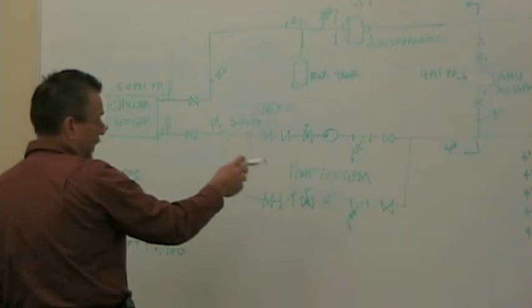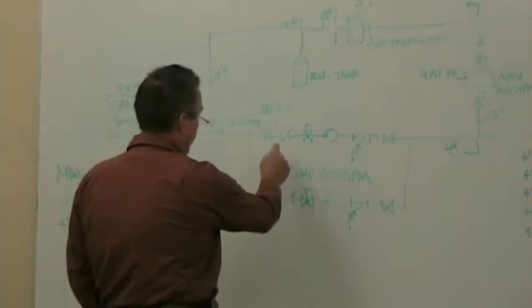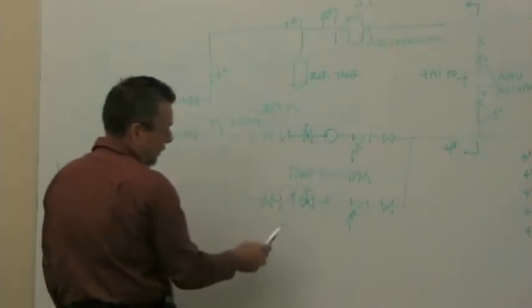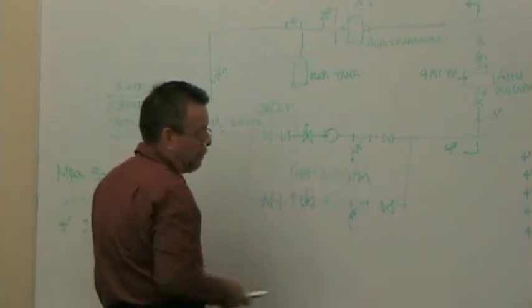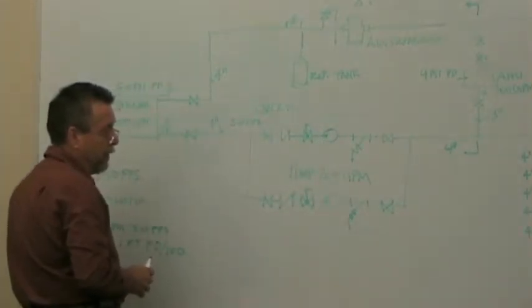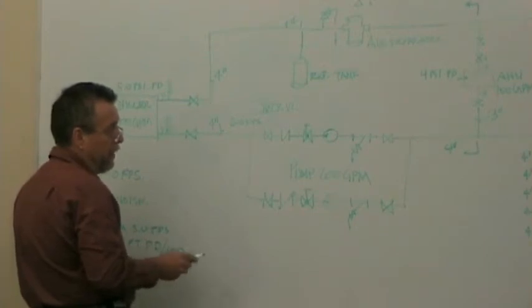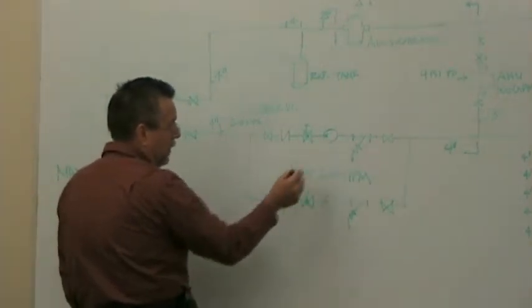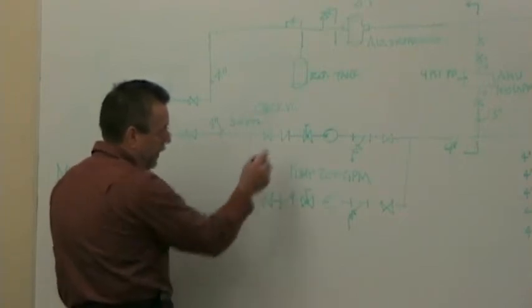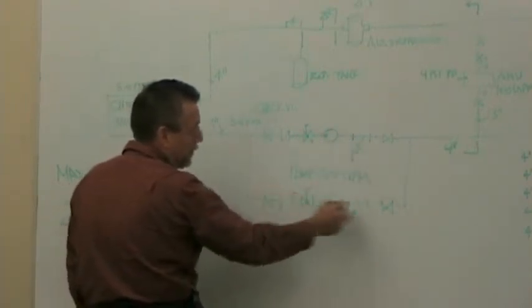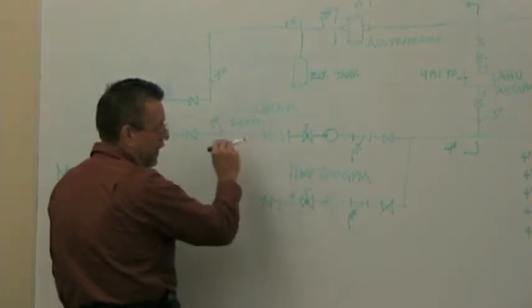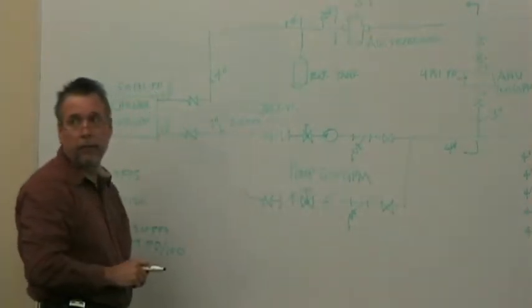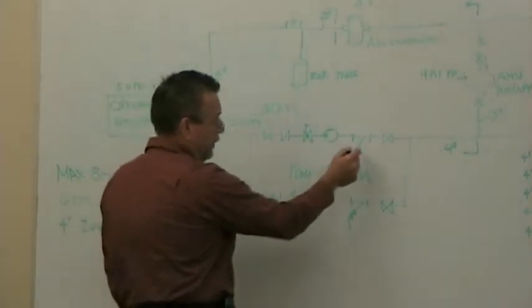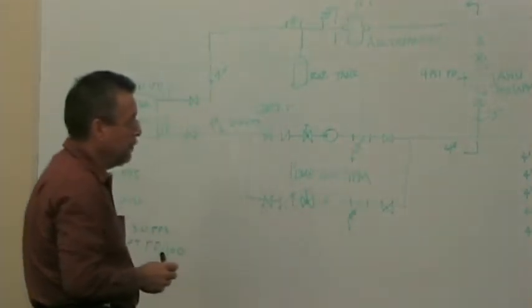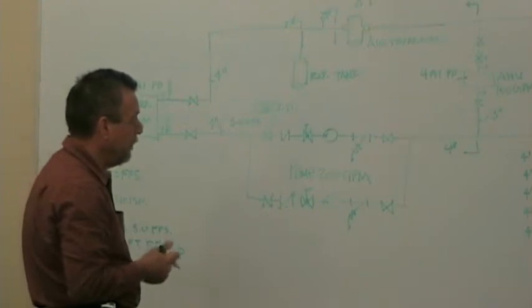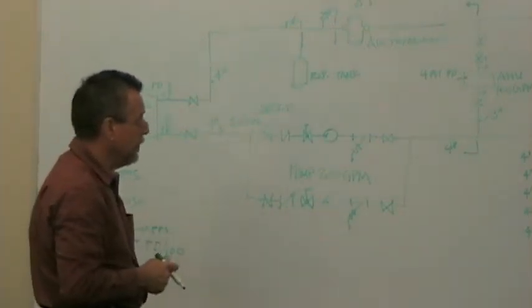So I covered everything. I've got strainers, I've got check valves. The reason for that check valve again, these are parallel pumps that could operate at the same time. They could operate independently, but even if this pump is off and that pump is on, if I don't have a check valve right here, some of the water is just going to go just like that. The reason for that check valve is to prevent backwards flow when you have parallel pumps. The strainer has a screen in it, and it protects against any large trash in the pipe getting to the pump and getting back to the coils.